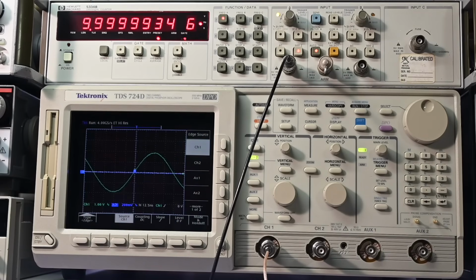Now, if I go down here and actually make a change, I'm going to start increasing this by 1 hertz higher, very small increments, 2 hertz higher. So it's getting a little bit closer. Okay, right there, it's very close. Right there. Okay, so that's 6.6 hertz higher on the display. So I rolled the frequency up just a little bit, 6.6 hertz. Once it's on that frequency, it is very stable, but it is off from the displayed value. Now, something else that we can do: go back here to 10 megahertz, like that.